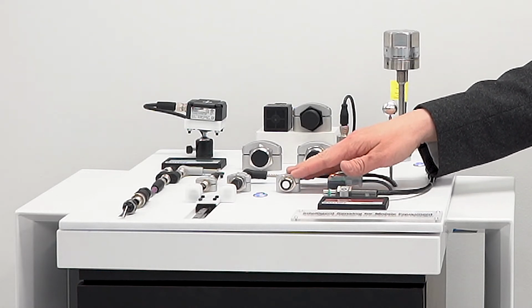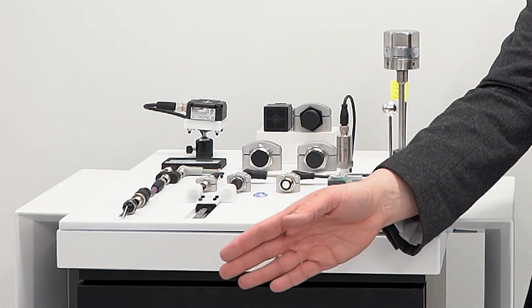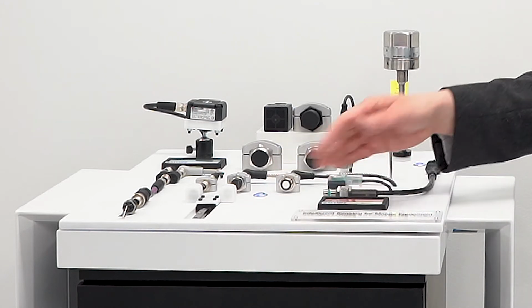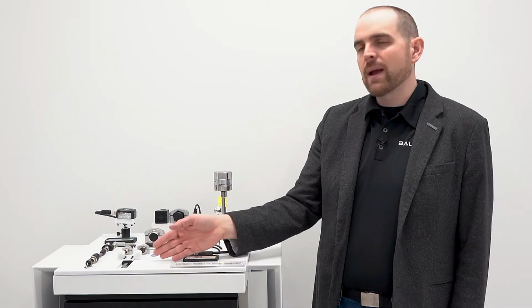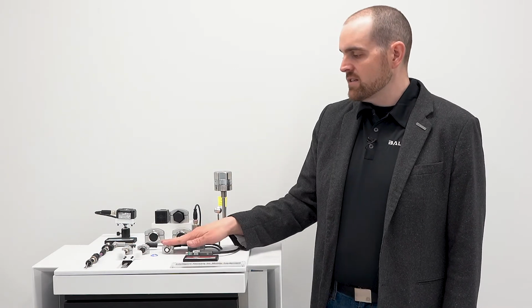The ultrasonic sensor uses sound waves to detect the presence and can provide an analog position value, a 4 to 20 milliamp signal, that gives you information about how close you are to the object. So that's a great option, using sound waves to detect the position and proximity to an object.